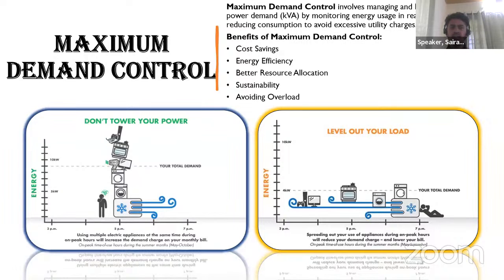So we can use maximum demand controllers, where a set point is set at the load end. If we are getting close to exceeding the contract demand, it will automatically turn off or optimize the loads, so that the demand won't go beyond the contract demand. The benefits of maximum demand control are cost savings, energy savings, better resource allocation, sustainability, meaning a reduction in emissions, and overloading is avoided at the grid end and also at the user end.